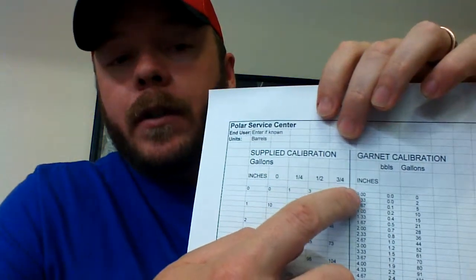So what I'm going to do is, since the programmer is at 0.00 inches, the programmer is asking me what calibration is linked to 0.00 inches, which based off of our chart, shows us 0.0. So I'm going to manually enter in that chart value, 0.0, and you can see it popped up there. As I typed it, it shows up. I have to hit enter to move on. You can see the inch value jumped up to 0.33 of an inch, so it's ready to receive the next calibration.